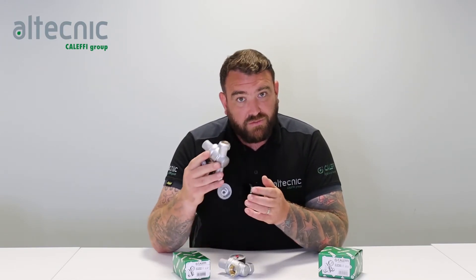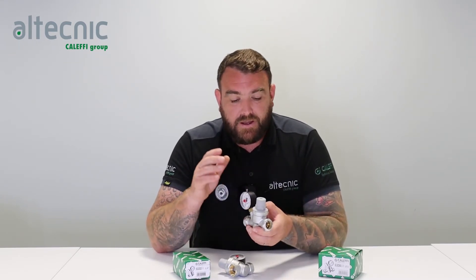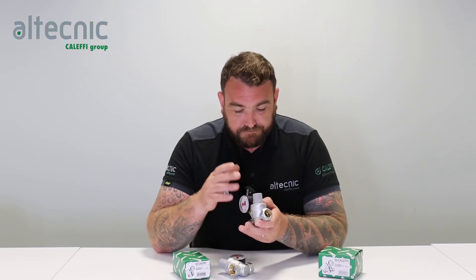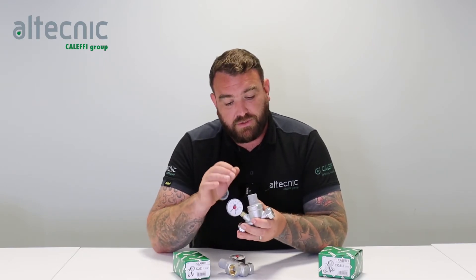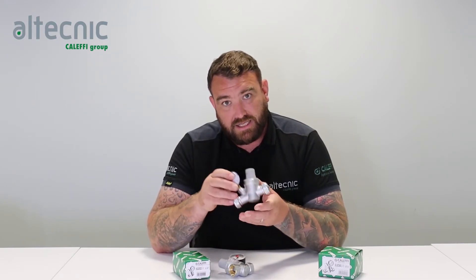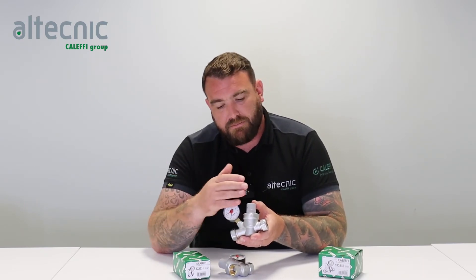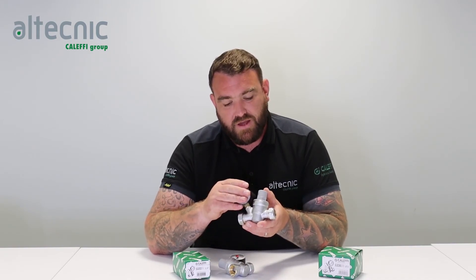The 533 range from Altecnic and Caleffi comes preset at three bar, and that is adjustable. On top of the valve there's a brass screw — to increase the pressure we turn it clockwise, and to decrease the pressure we turn it anti-clockwise. As this is a dynamically controlled valve, this should be done when there's an outlet open: open a tap, pull some water through it, start to adjust the valve, and you can see what pressure it's set to.